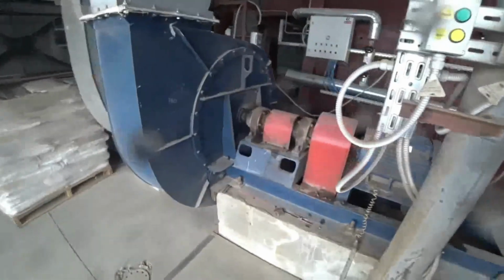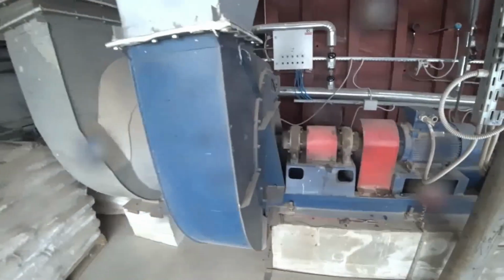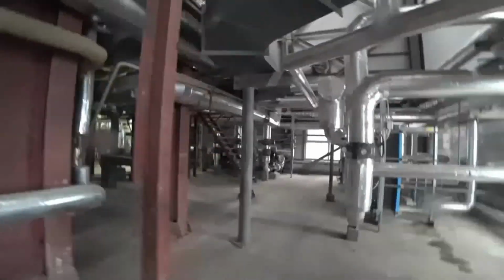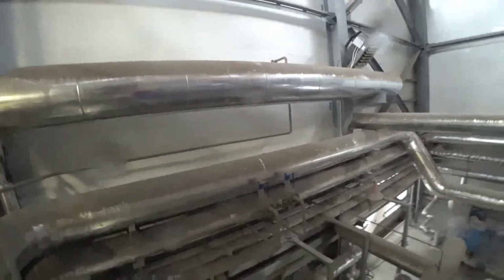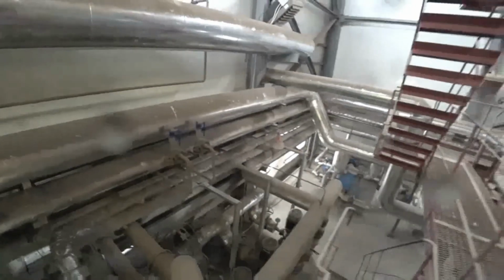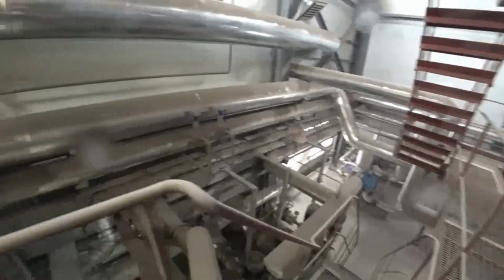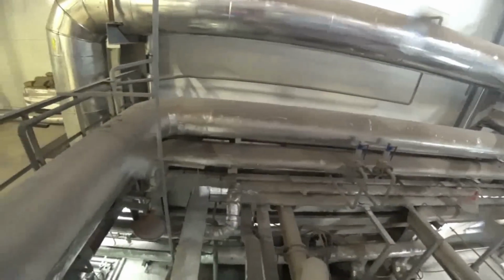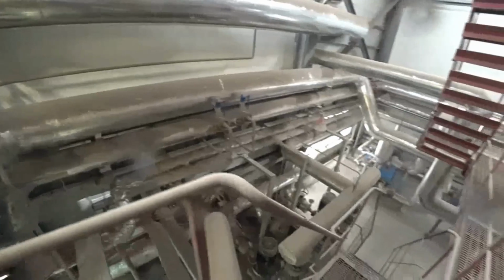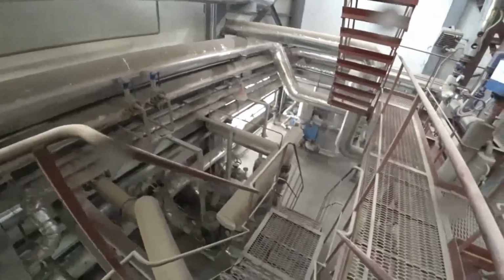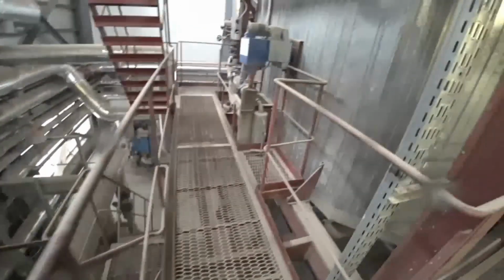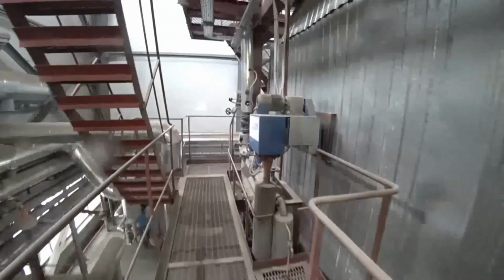Ukrainian-made secondary air fan. Let's go higher. We draw your attention to the noticeable layer of dust in the boiler room. This dust, ash, gets into the boiler room through open windows and supply ventilation from the side of the ash loading unit into the tractor trailer. Having reached this unit, we will clearly demonstrate everything to you.